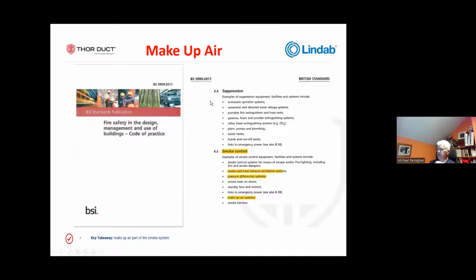The other thing to draw your attention to is smoke control. Sometimes because of the size of the fans, and sometimes because of the location of the ventilation requirement, you may not have enough air. And when you don't have enough air, the fan can get into trouble and it can burn itself out. It can be exhausted without the proper air. So you have to provide what we call makeup air. And so makeup air is considered part of the smoke control system. So the ducts used to provide makeup air have to be fire resistant ducts because they need to stay open to allow air in so the smoke system works.